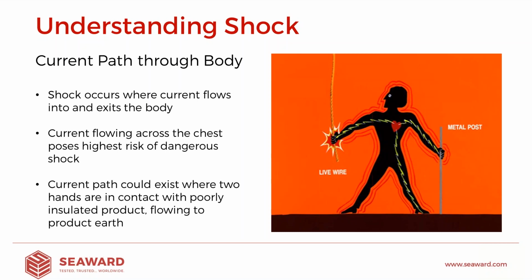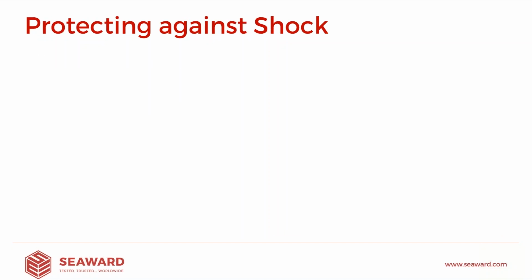It's also true that current could flow across the chest from hand to hand. So it may be that we're working on a product, we're in contact with a live conductor with one hand, and potentially we may be resting the other hand on the chassis, and that chassis of the product is grounded and flows away to earth. Again, if we were to come into contact with live current, that will flow through the body onto the chassis of the product through our other hand and away to ground via the product's ground path. Again, that could really take it across the chest and be problematic for us. So we need to consider these factors when we're thinking about designing a safe working area.